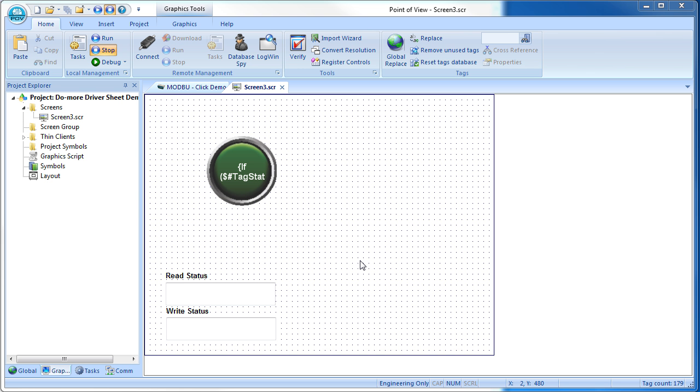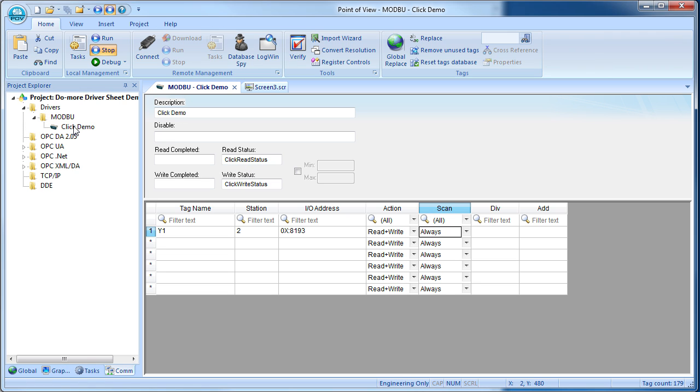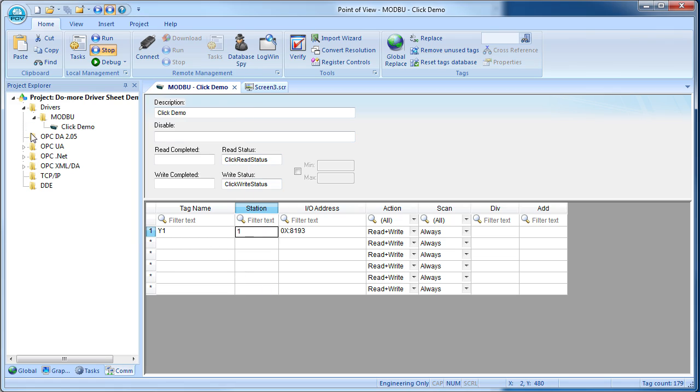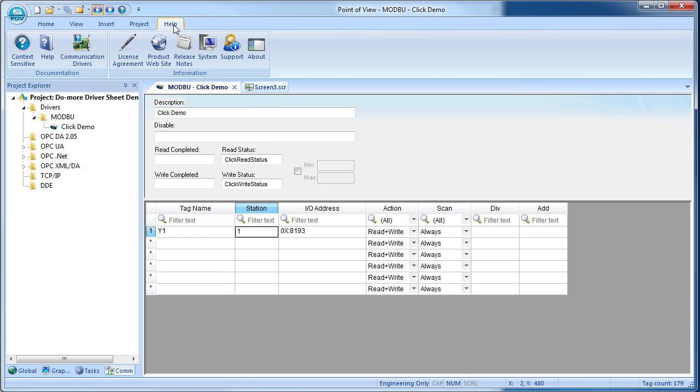Let's intentionally add an issue just so we can see how to debug it. Let's go back to the driver sheet and pretend that we forgot to tell Point of View to go to node 2 on the Click. Save all, run it. Ah, look, we got a minus 15 error.